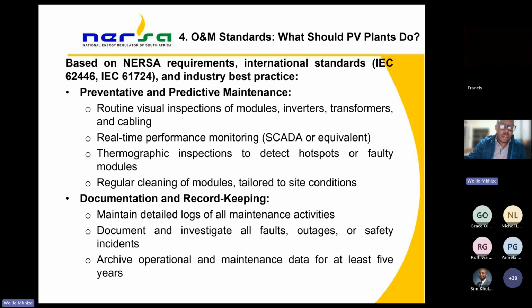It also means we need real-time performance monitoring through SCADA or equivalent equipment. Thermographic inspections to detect hotspots or faulty modules are very important as part of routine maintenance, at least every 3 months. Regular cleaning of modules tailored to site conditions is also important — for places more prone to dust, more regular cleaning of the PV modules is required. I think this is all just common sense.